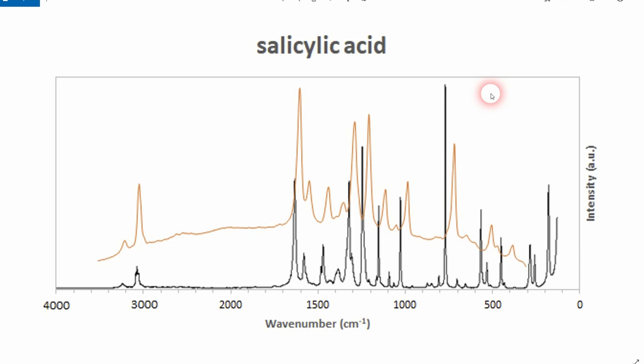So you can clearly see that all the peaks are there. They are a bit broader. That's normal. It's because of the starter edition. The resolution you can expect from this spectrometer is about 34 centimeters minus one.